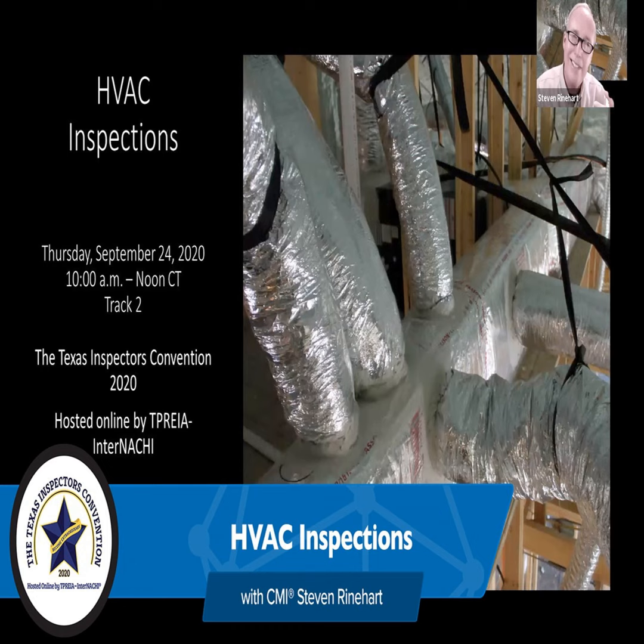Couple of things, absence of a disconnect outside, guys have gotten in trouble for it. You've got to have a disconnect. It may not be dedicated, it could be a breaker in the service entrance panel if it's within 25 feet. Deficiencies, that's where somebody got noted for having rust in the secondary pan and didn't report it. The standard says evidence of water, I can understand.